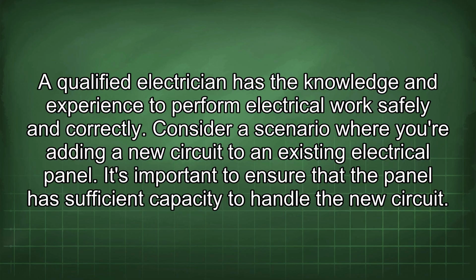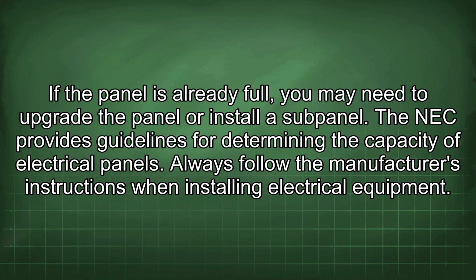Consider a scenario where you're adding a new circuit to an existing electrical panel. It's important to ensure that the panel has sufficient capacity to handle the new circuit. If the panel is already full, you may need to upgrade the panel or install a sub-panel. The NEC provides guidelines for determining the capacity of electrical panels.